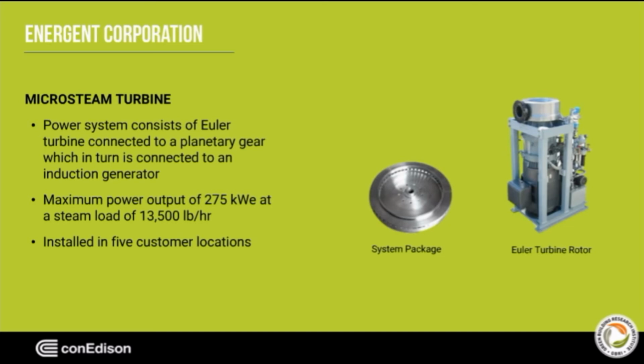The system accepts steam loads between the range of 4,000 to 20,000 pounds per hour. The maximum power of 275 kW can be produced with a steam load of at least 13,500 pounds per hour. This system is ideal for our larger customers that have higher steam loads during the summer period in order to benefit the most from the electric energy produced. We currently have 5 customers that have installed the micro steam turbine and have been able to benefit from the electric savings.